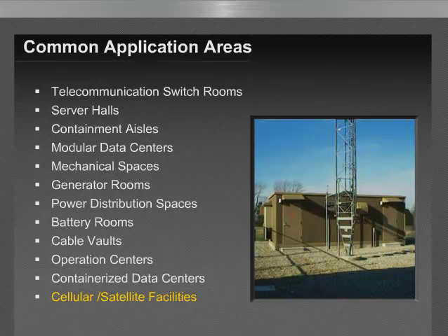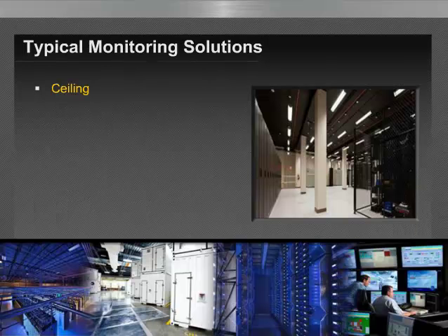Now let's look more specifically at the typical monitoring solutions for each of these types of areas, which is somewhat of a summary of what we've talked about in the previous illustrations. We look at ceiling detection, and that is placement of the sampling pipe at the ceiling for area detection. And again, that might be at every 200 square feet.